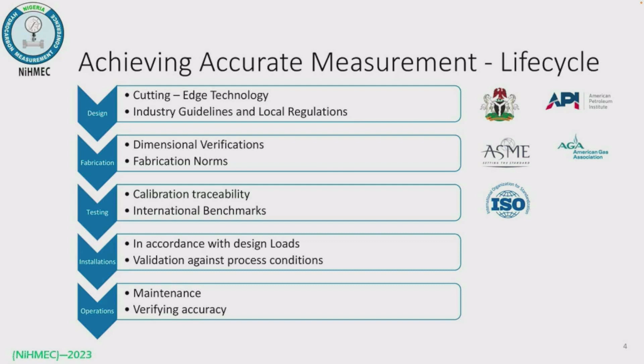Second, during fabrication, it's very important to perform dimensional verifications. For example, with an orifice metering system, the upstream section is a critical part of fabrication, requiring accurate measurement of dimensions and internal roundness, since many factors there can impact gas measurement.